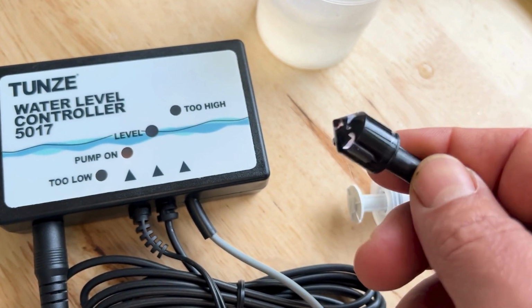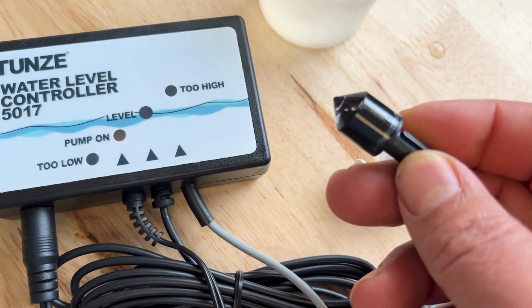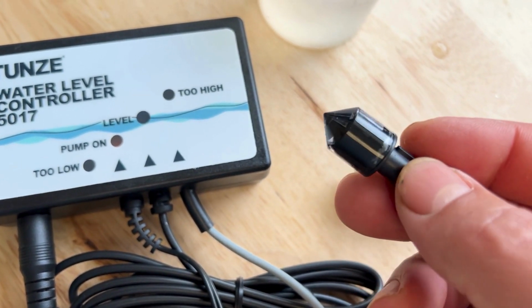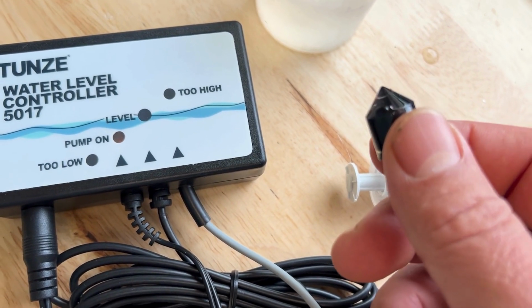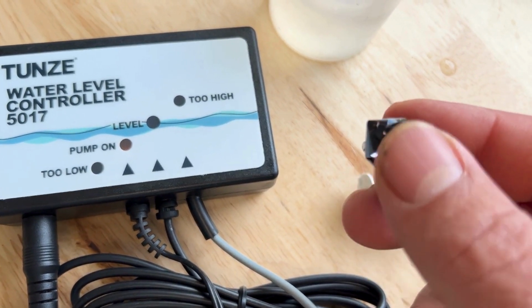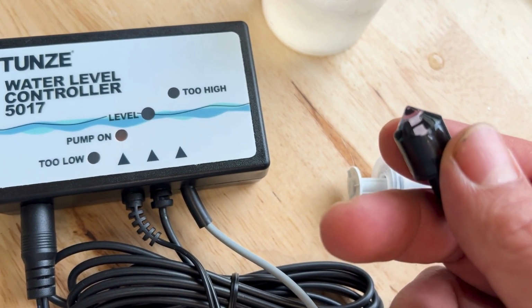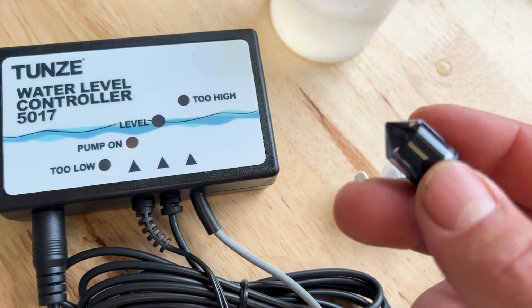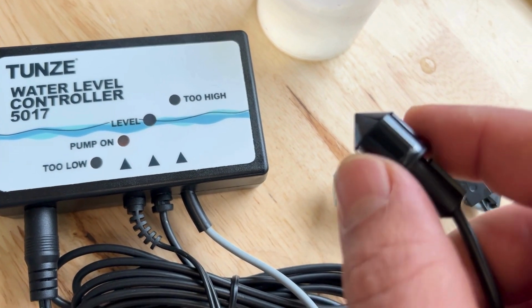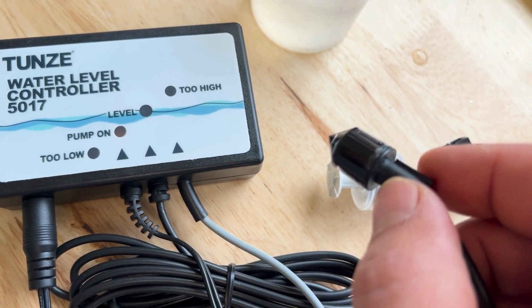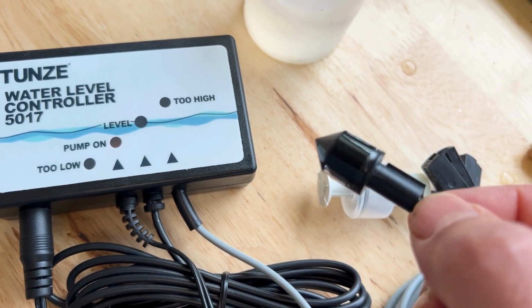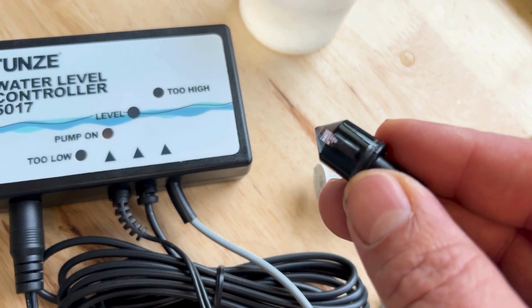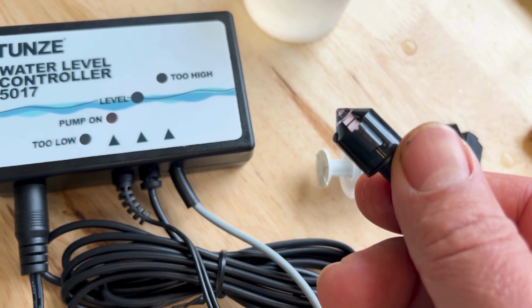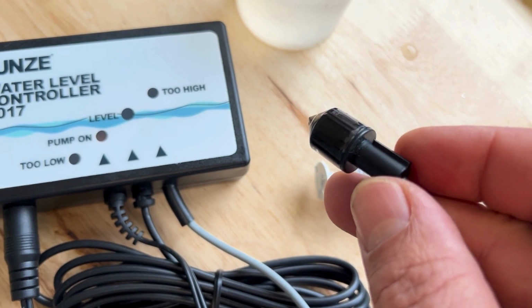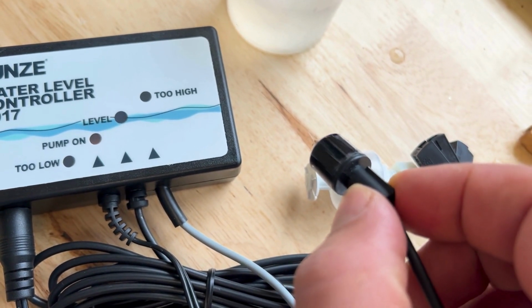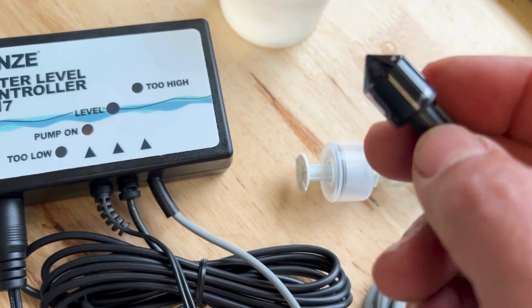Your optic sensor needs to be shiny clean. This is a new sensor. I sometimes get some odd ones where people are insistent that there's debris or something inside the sensor. That's just not possible the way these sensors are made. This lens is put on this black cap after the wire is pushed through and the LEDs inside are wired up. There's an infrared receiver and an infrared LED inside. And then this entire unit is filled with polyurethane, so it is a sealed unit.